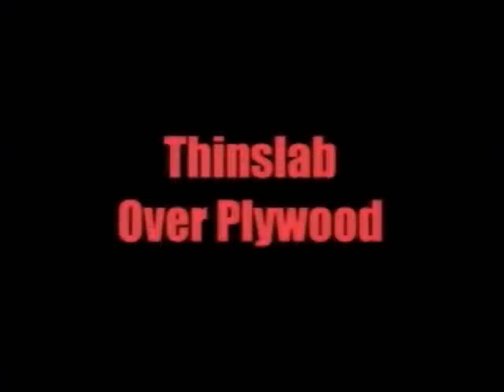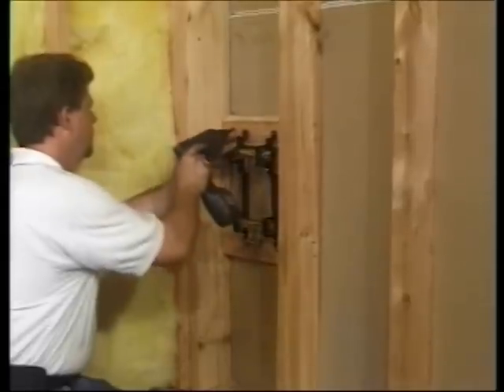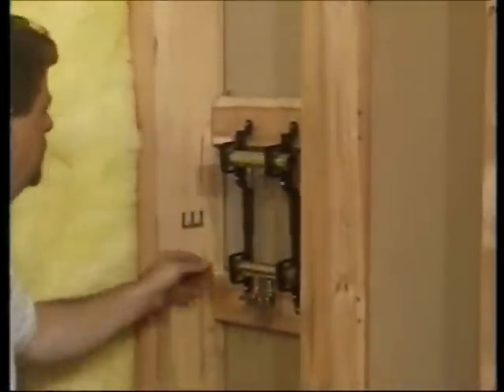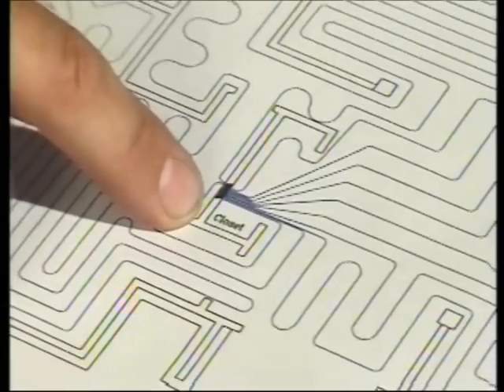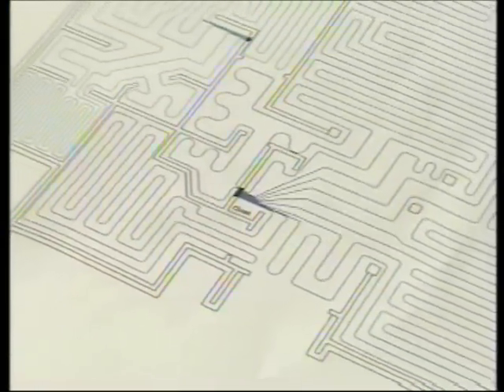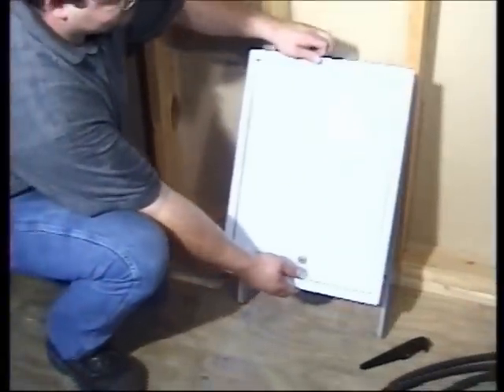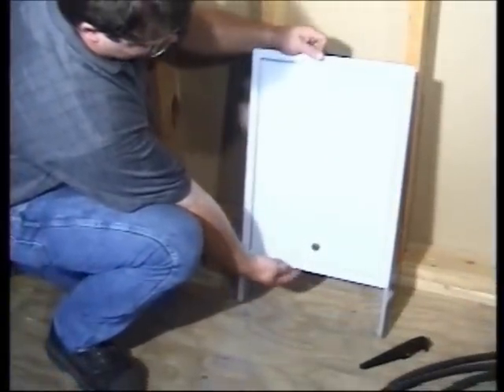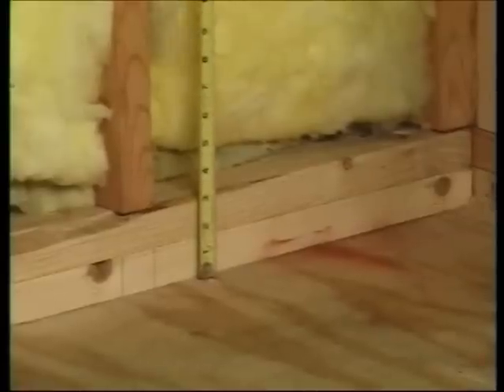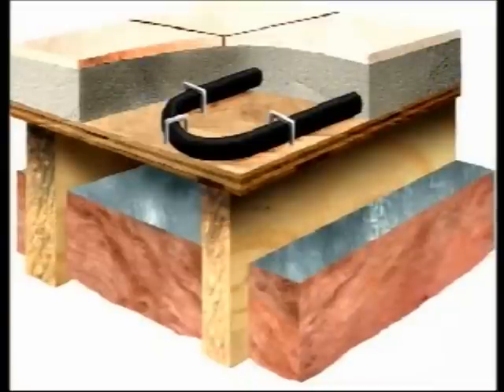Next, let's install Onix in a thin slab over plywood. Manifolds are generally installed in a wall cavity with an access panel. Other good locations include the back of a closet, under a cabinet, or in a vanity. Manifold boxes complete with an access door are also a popular option. Remember to double plate the interior walls and plan for the weight of one and a half inch depth of masonry when sizing your flooring members.